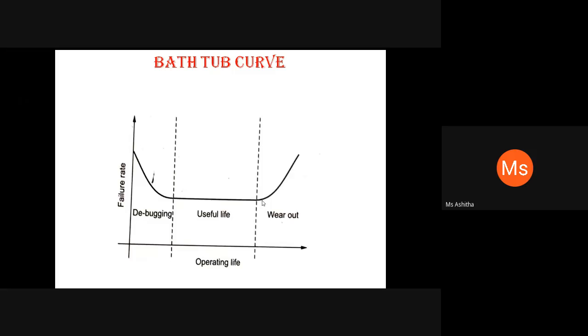In the wear out period, or old age, the failure rate increases, as you can observe in the curve. The repairs in this period are very costly, and therefore it is preferable to replace the component with a new one. Normally the power system is operated in the useful life for a long time, with proper periodic maintenance. So compared to the debugging and wear out periods, the useful life is the most useful period.